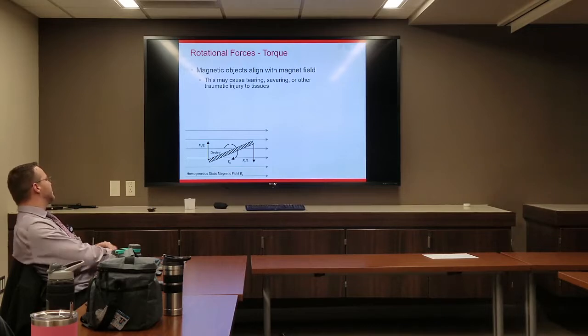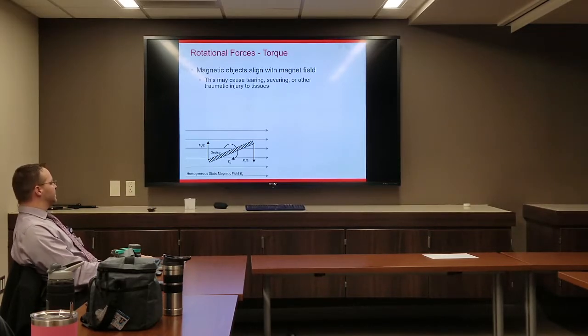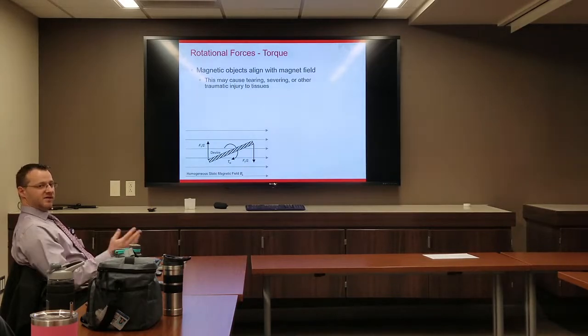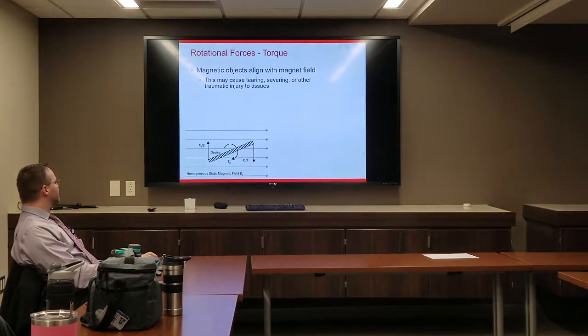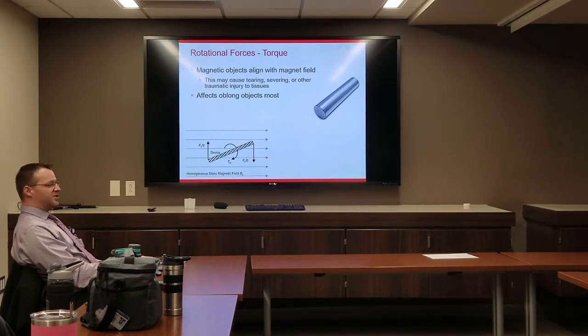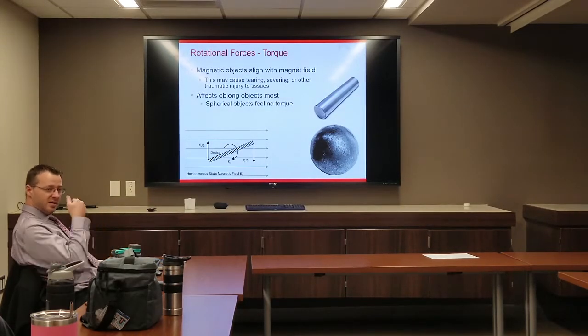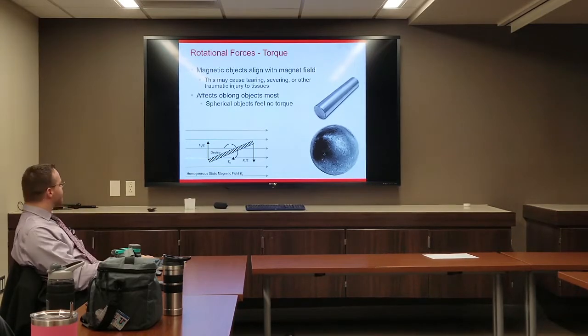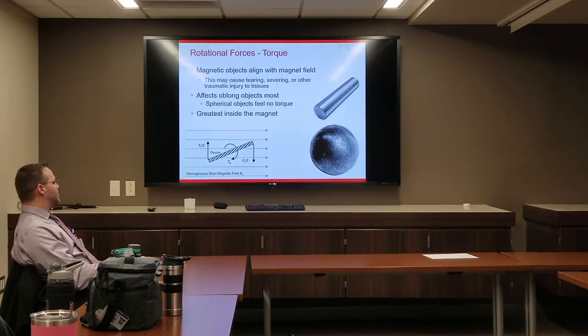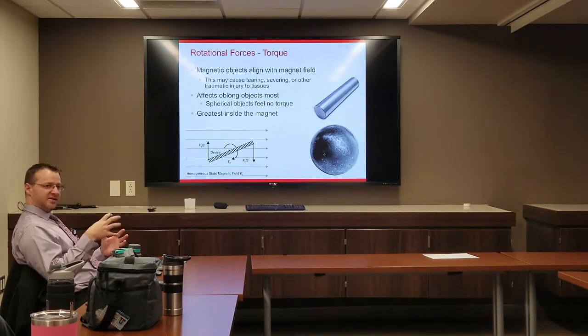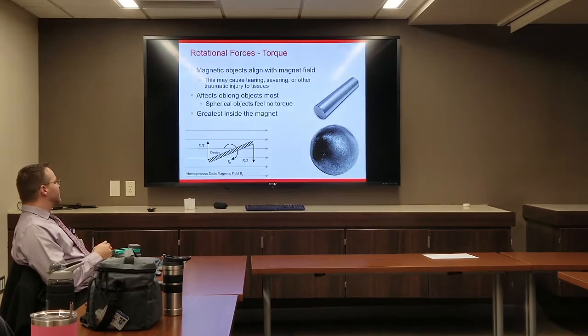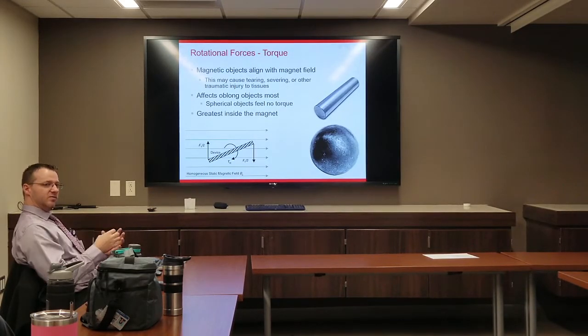For rotational forces: magnetic objects will attempt to align with the magnetic field. This can cause tearing, severing, or traumatic injury to tissues if the object twists to align with the field. Oblong objects are affected most; a perfect sphere would experience no torque, though it would still experience translational forces. Unlike translational force (which is greatest just outside the magnet), torque force increases as you approach stronger magnetic fields and is strongest at isocenter.